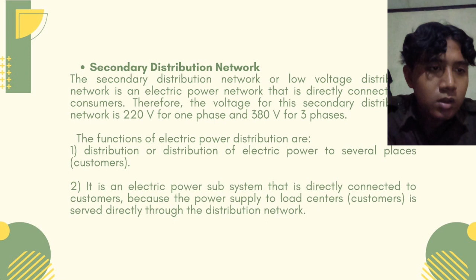Classification of electric power distribution channels. In general, electric power lines or distribution lines can be classified as follows. According to the voltage value, primary distribution channels are located on the primary side of the distribution transformer, namely between the secondary points of the substation transformer and the primary point of the distribution transformer. This line has a medium voltage of 20 kilovolt. A 70 kilovolt or 150 kilovolt electricity network, if it directly serves customers, can be called a distribution network. Secondary distribution channels are located on the secondary side of the distribution transformer, namely between the secondary points and the branch point to the load.